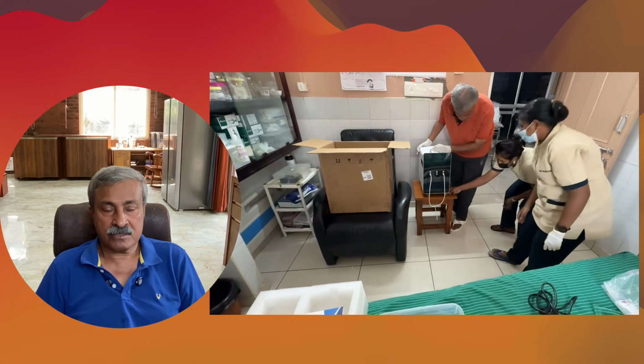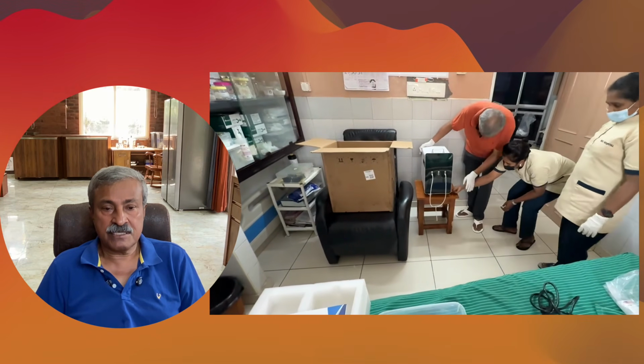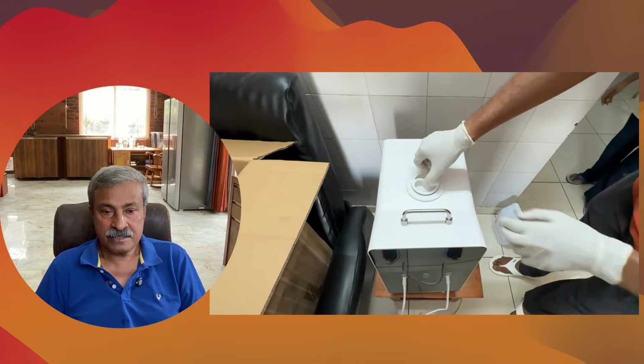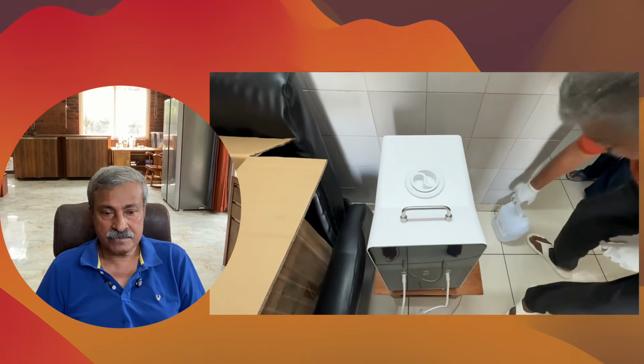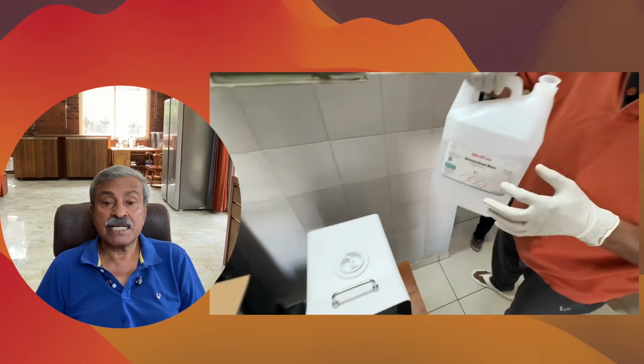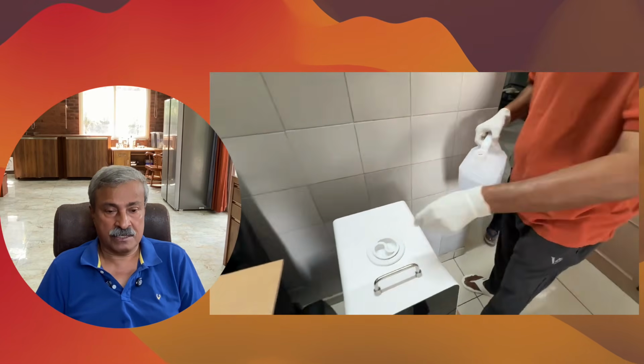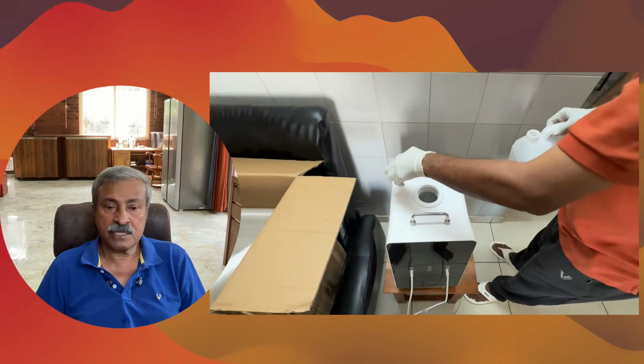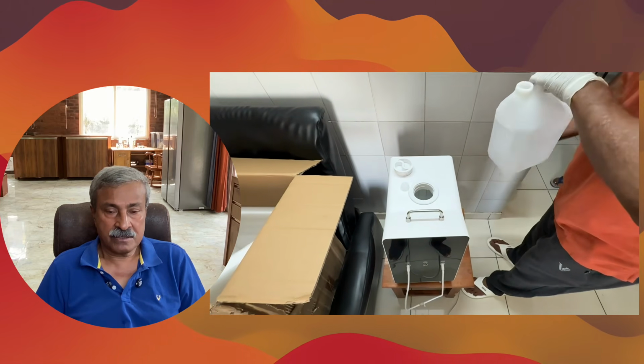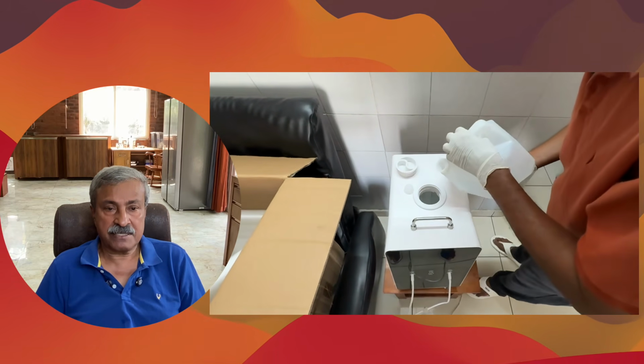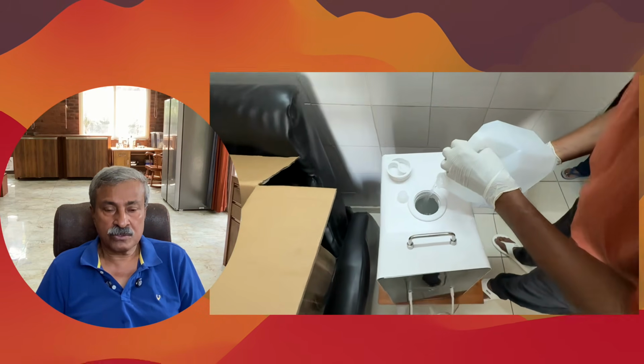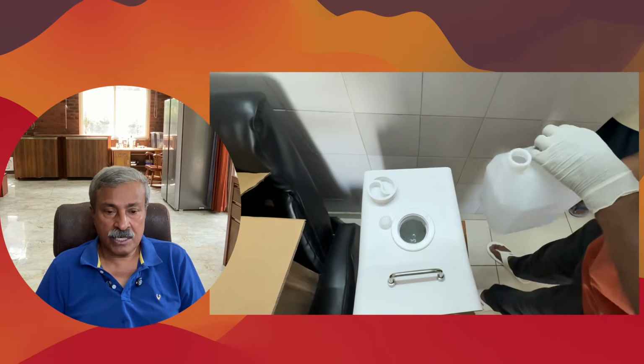The wheels are locked, the machine is stabilized in a proper position. We need medical grade distilled water. Do not use mineral water or ordinary water. The machine splits H2O into H2 and O2.